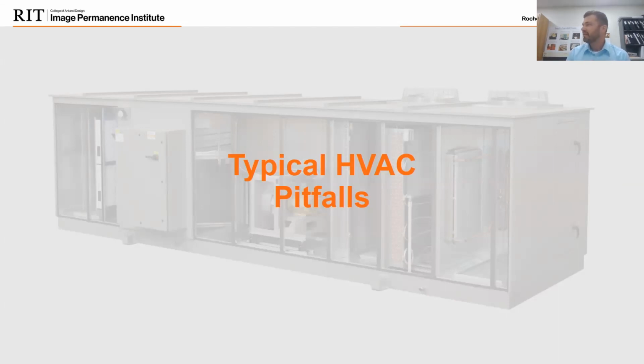And then I think you may have addressed this just towards the end, but does a dedicated outside air unit reduce energy costs? The answer is yes and no. Having that unit, you're going to have more cost for operating that individual unit. Obviously, you have another unit that's going to be using energy to heat, to cool. But in the same respect, you are no longer doing the extra work to dehumidify, to humidify at the units, which reduces some of the strain or stress on those units, if you will.